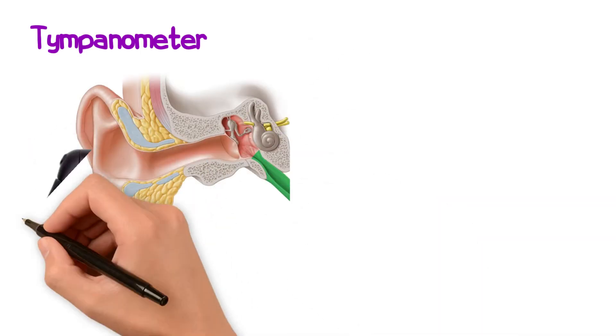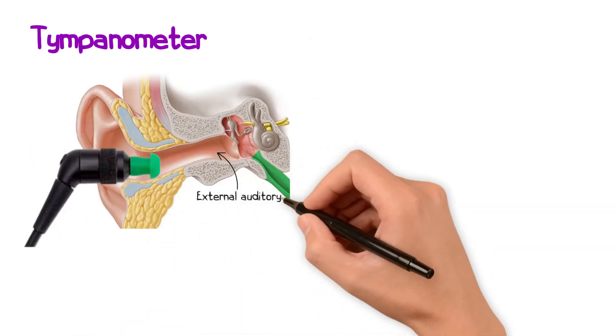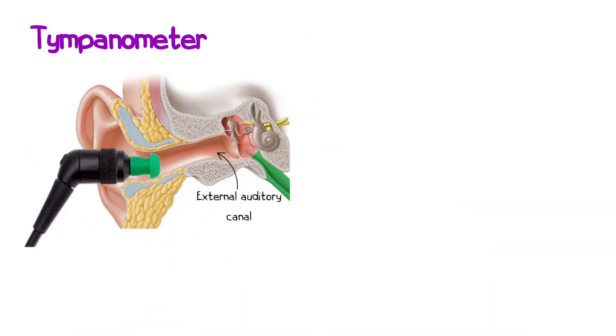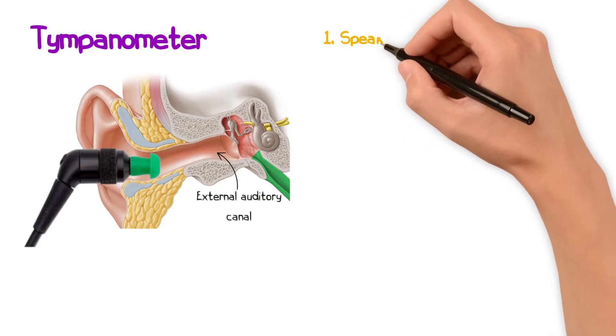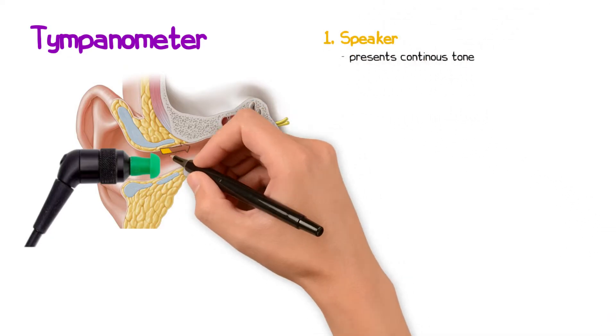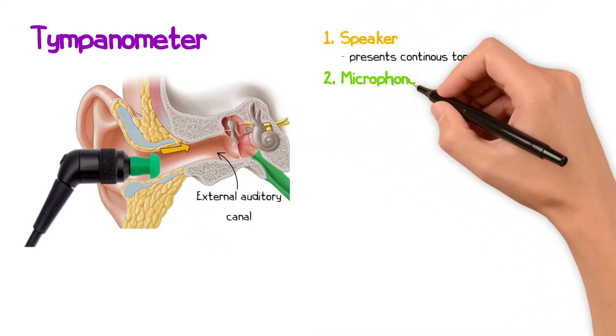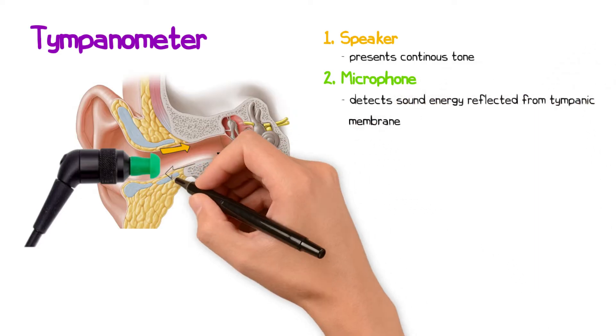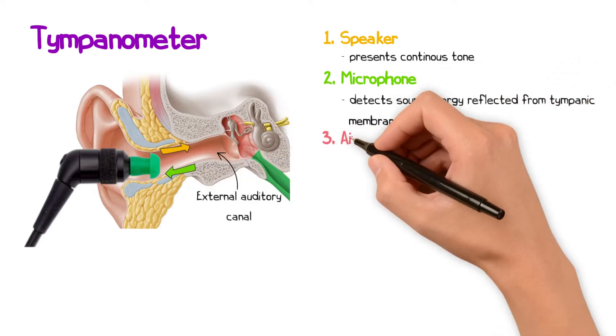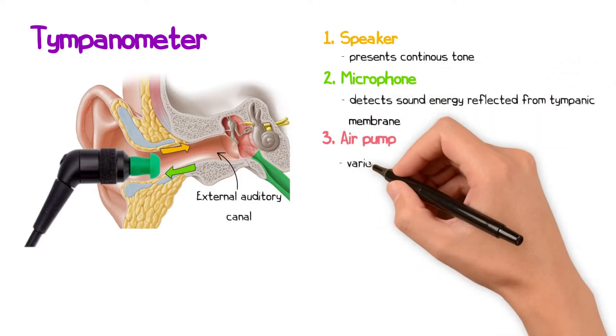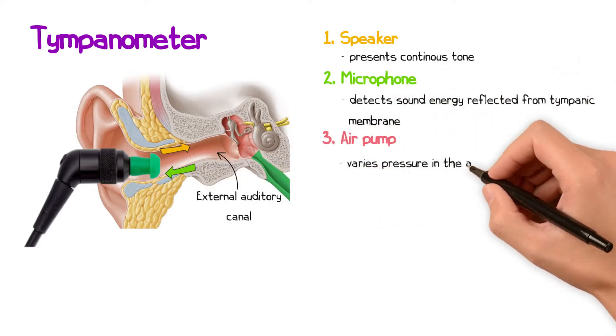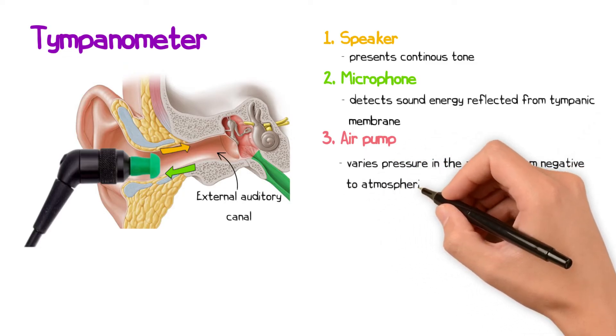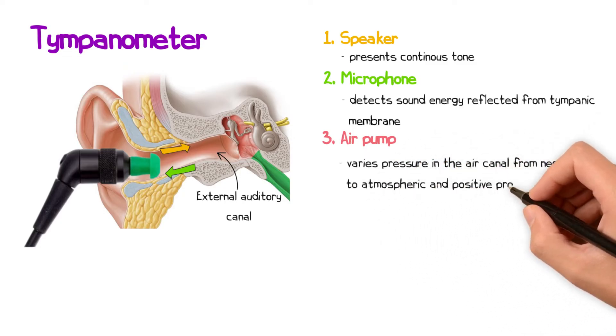A tympanometer consists of a probe that is inserted into the external auditory canal. This probe contains a speaker that presents a continuous tone, a microphone that detects sound energy reflected from the tympanic membrane, and an air pump that varies the pressure in the ear canal from negative through to atmospheric and positive pressure.